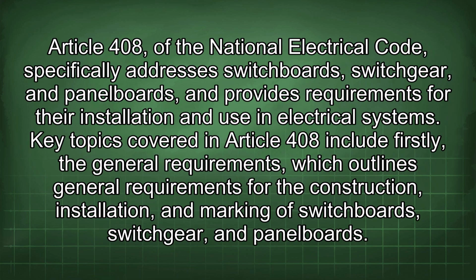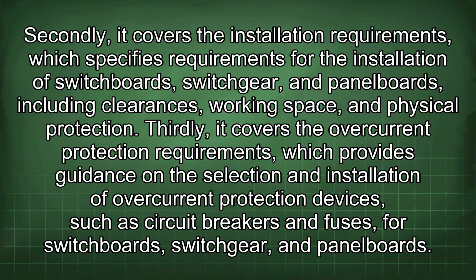Article 408 of the National Electrical Code specifically addresses switchboards, switchgear, and panel boards, and provides requirements for their installation and use in electrical systems. Key topics covered in Article 408 include firstly the general requirements, which outlines general requirements for the construction, installation, and marking of switchboards, switchgear, and panel boards. Secondly, it covers the installation requirements, which specifies requirements for the installation of switchboards, switchgear, and panel boards, including clearances, working space, and physical protection. Thirdly, it covers the overcurrent protection requirements, which provides guidance on the selection and installation of overcurrent protection devices, such as circuit breakers and fuses, for switchboards, switchgear, and panel boards.